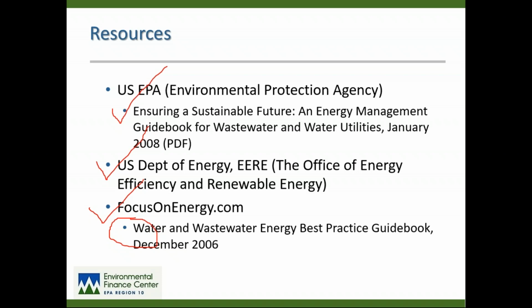The next question we received is, how do adjustable frequency drives affect the efficiency of pump motors? Does this negate some of the waste of oversizing motors? This does. Variable frequency drives or variable speed drives, they're kind of synonymous. In water pumping applications, they almost always provide energy savings, and they do that for various reasons. Number one, they can ramp a motor speed up or down depending on conditions in the system. Rather than having a motor cycling on and off to meet demand in the system, a variable frequency drive is like the throttle on a car. You don't drive your car with your gas pedal floored and then pump the brakes to regulate your speed. You want to just slow the car down. That's what a VFD does.